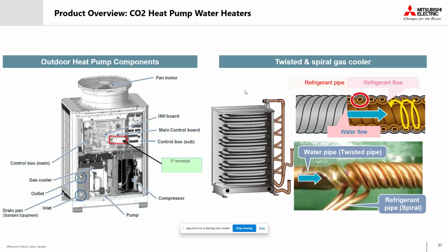Inside of the system, you'll also find a twisted spiral gas cooler. This is a heat exchanger that's unique to this particular CO2 heat pump, and it's specifically designed to work with CO2 in its supercritical state, which maximizes how efficiently the heat gets transferred from the refrigerant to our water loop. This unique component is one of the reasons CO2 heat pumps can deliver such high water temperatures at a very high delta T, sometimes over 50 degrees Fahrenheit, or up to 100 degrees Fahrenheit in some cases, all within what I would say is a relatively small footprint for that outdoor chassis.